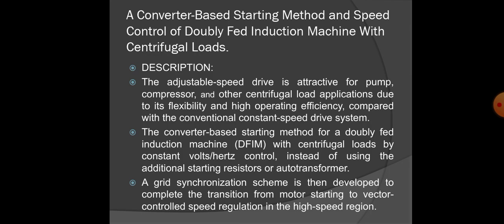Today, my topic is converter based starting methods and speed control of a double fed induction machine with centrifugal loads. The adjustable speed drive is attractive for pump, compressor and other centrifugal load applications due to its flexibility and high operating efficiency compared with the conventional constant speed drive system.